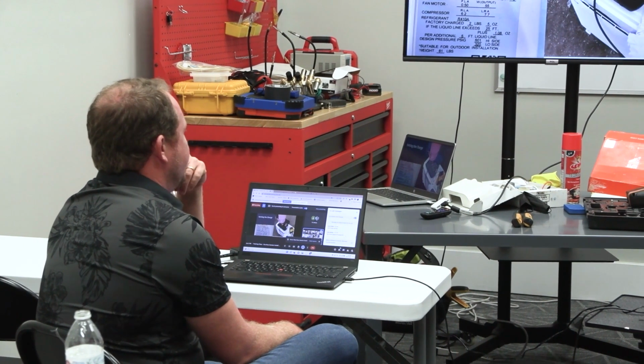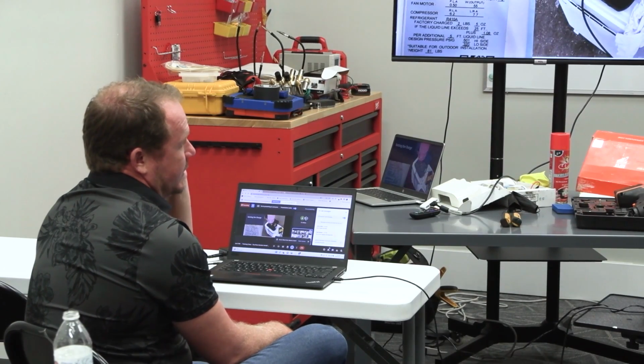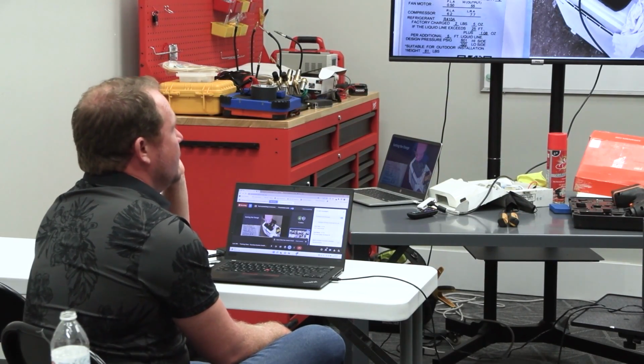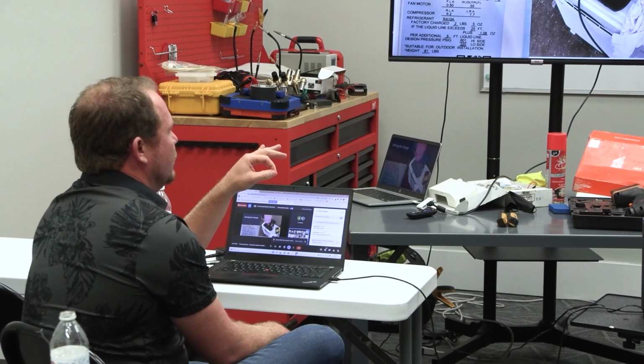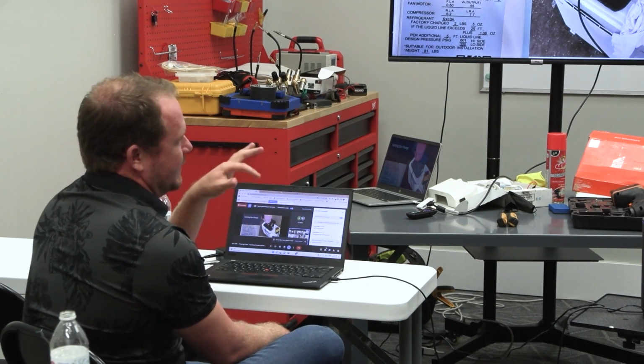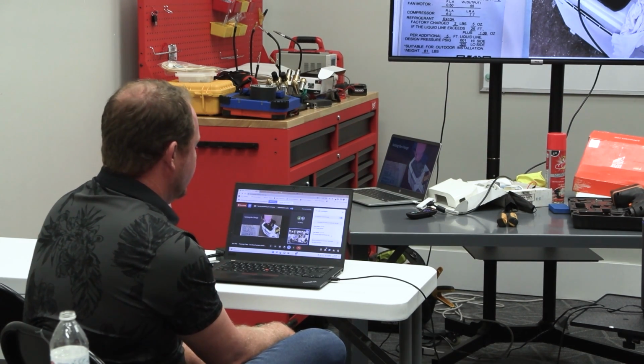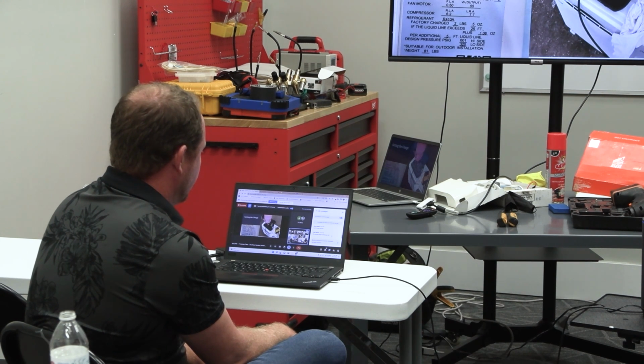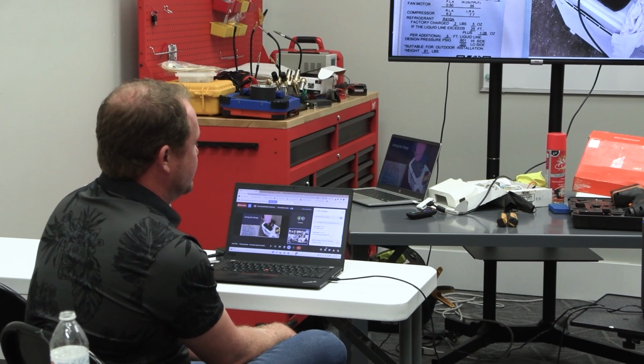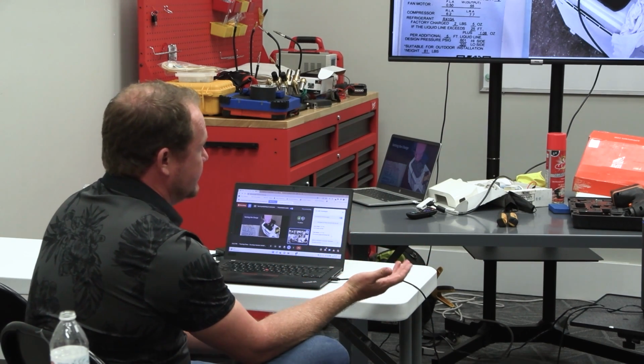Yeah, and again, this is pretty basic math. It's the amount of refrigerant that the liquid line can hold per 5 feet. So you can actually use the charging calculator on my site as well. But then you wouldn't necessarily know what the initial line length is for that manufacturer. So you're not probably going to get away with not reading that manual. But when in doubt, you can look it up on our app. Chad says the micron gauge will always tell, which is also kind of supporting what Aaron said.